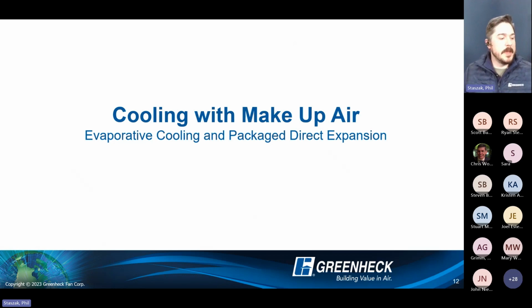All right, now cooling with makeup air. I kind of brought this up at the beginning where cooling is just not as common in makeup air applications. We really see this around the kitchen market. And the reason for that is because everything coming into that building is typically being exhausted right back out. So it's kind of a waste of energy, whether you're looking at heating or cooling.